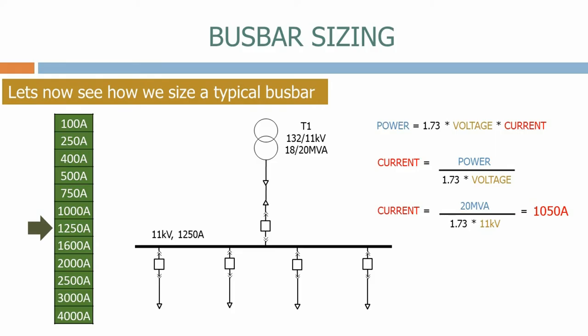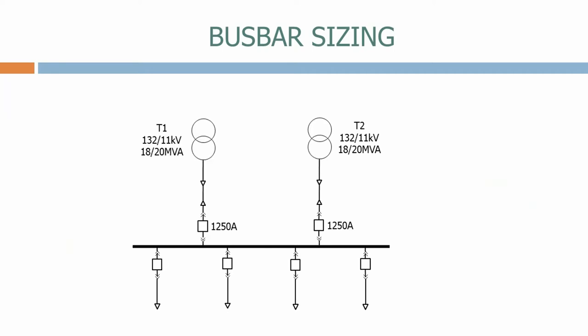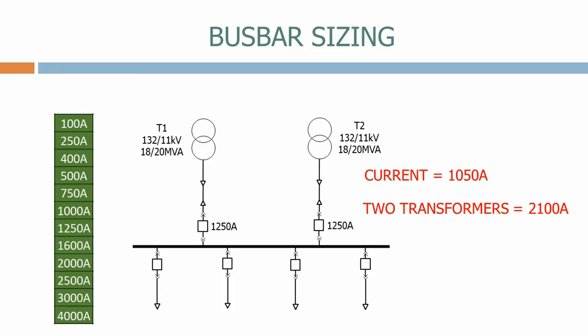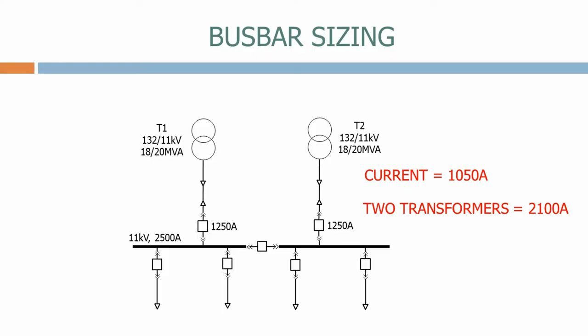As the busbar is rated at 1250 amps, we normally give the transformer incomer circuit breaker the same rating. Let's now look at two transformers feeding a busbar. We've set the circuit breaker rating for each transformer at 1250 amps based on the maximum current rating for each transformer. The current for each transformer is 1050 amps, so two transformers give 2100 amps. Looking at our standard busbar rating table, we'll choose a busbar rating of 2500 amps. The busbar section breaker is normally made the same rating as the busbar, which is 2500 amps.